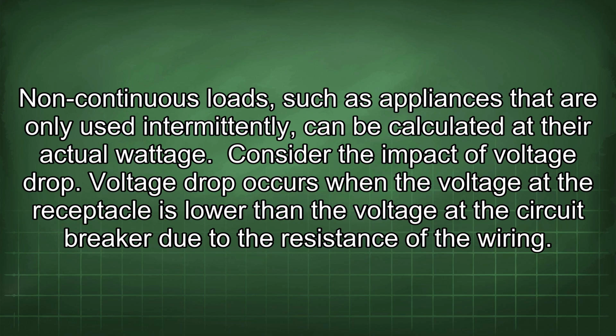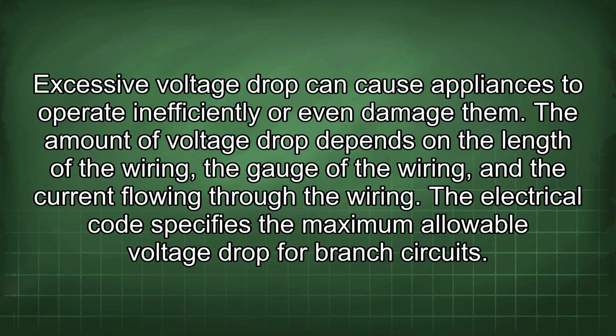Consider the impact of voltage drop. Voltage drop occurs when the voltage at the receptacle is lower than the voltage at the circuit breaker due to the resistance of the wiring. Excessive voltage drop can cause appliances to operate inefficiently or even damage them. The amount of voltage drop depends on the length of the wiring, the gauge of the wiring, and the current flowing through the wiring.